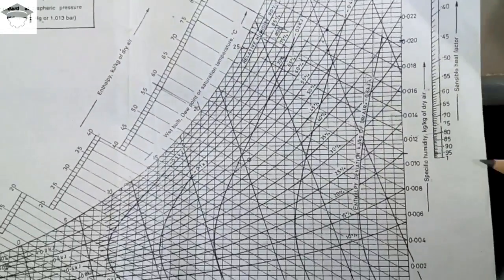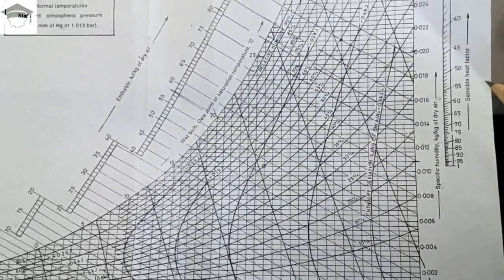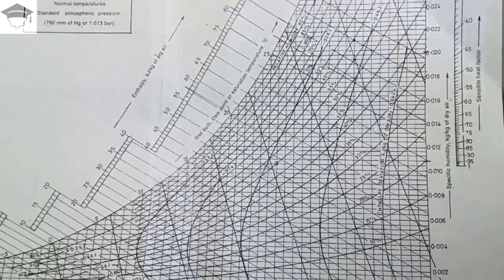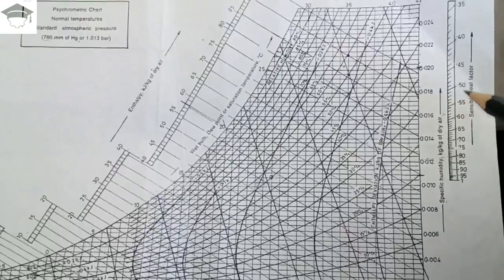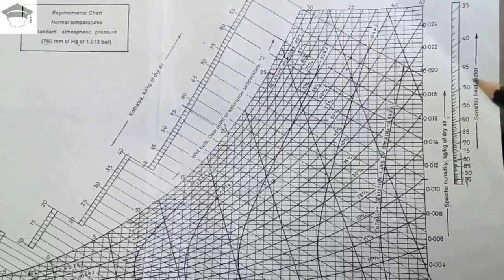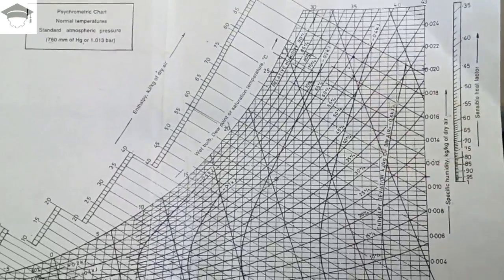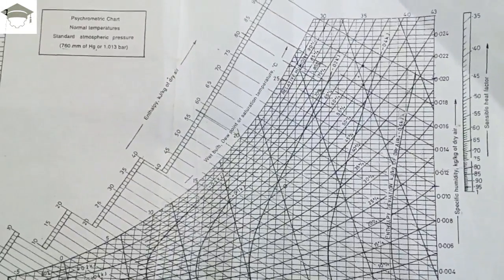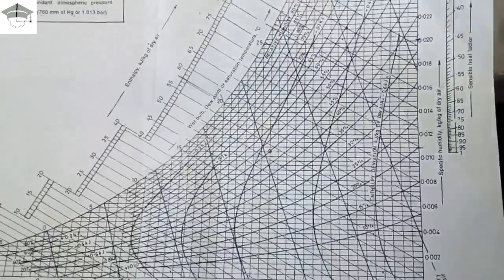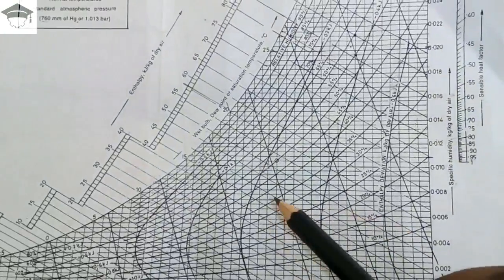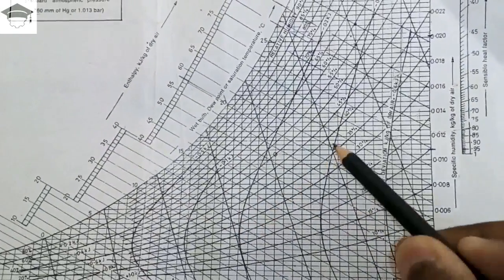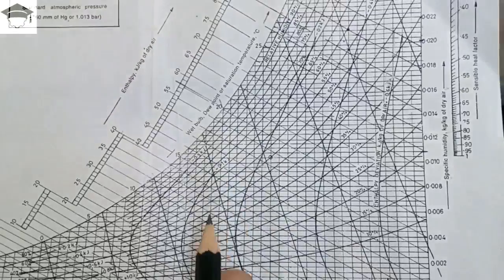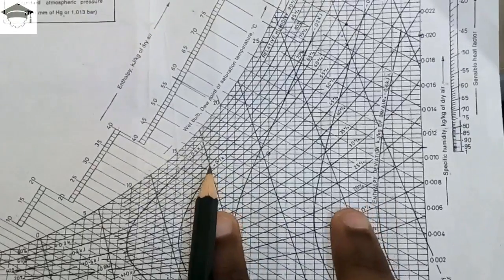The sensible heat factor is commonly asked about in exam questions. Sensible heat factor equals sensible heat divided by the sum of latent heat plus sensible heat. With two points on the chart joined by a line, the horizontal component represents sensible heat and the vertical component represents latent heat, giving the total heat.